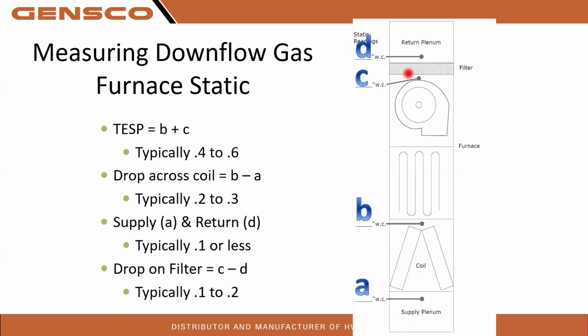But with these coils, so we got our furnace, we got a heat exchanger right here. There on our coils, our gas is coming into the coil right about here. So we can actually put our probe in that hole. We don't have to drill this hole, and we will be in the airstream before the evap. So keep that in mind. That'll speed you up. We don't have to drill a hole in a downflow application. Let's just use that hole on the gas side of the evaporator coil.